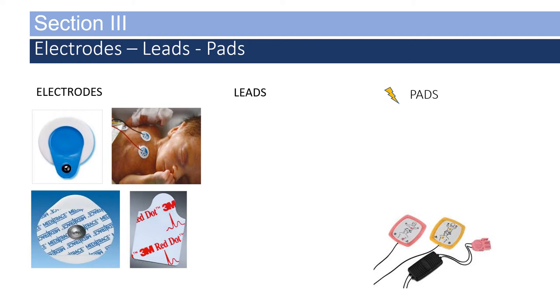Electrodes are either round or square. They have a gel diameter of approximately 16 millimeters and a silver-silver chloride diameter of 10 millimeters, surrounded by an adhesive medium. They are available in infant, child, and adult sizes — so don't cut electrodes to fit a smaller patient. There are also resting electrodes that don't have a metal clip; instead, wires are clipped to the tab at the end. These are commonly used in clinics, emergency departments, or hospitals. They last longer on the patient and don't show up as much during X-ray or other radiology.